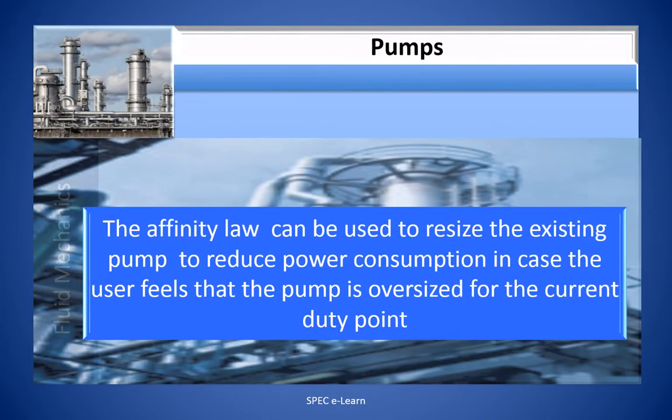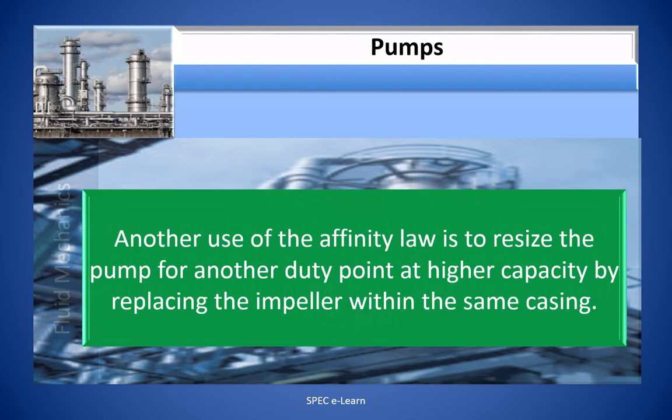The affinity law can be used to resize the existing pump to reduce power consumption in case the user feels that the pump is oversized for the current duty point. Another use of the affinity law is to resize the pump for another duty point at higher capacity by replacing the impeller within the same pump casing.